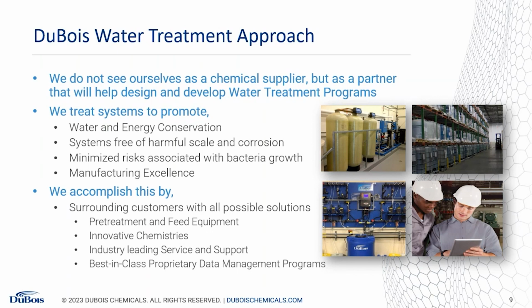So the highest quality feed equipment, oftentimes that has ways to measure what we're feeding and what we're controlling in terms of conductivity, pH, all system parameters, have those functions so they can communicate online, so we can see our data and how the system's running from wherever we are. Pre-treatment equipment such as softeners and dealkalizers and filtration that can help change that quality of water up front.